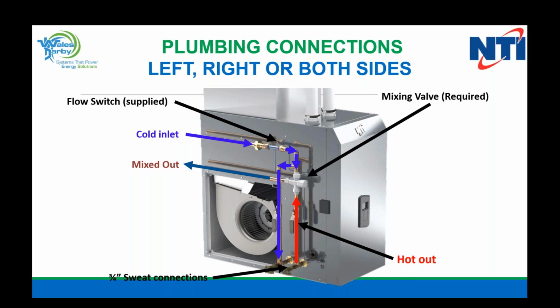There's that right there that you're seeing on the side of the unit with the mix valve and everything. NTI sells that as a kit. So you would just plug in your adapters to the right or left hand side. There's a clip on the inside to clip them in place. You would do your soldering before you clip them in, because there is a rubber O-ring. So you'll solder your pipe in, put them into the side of the unit, put your clips on, and hang your hot and cold water outlet to the house.